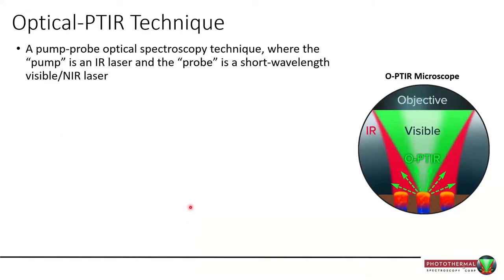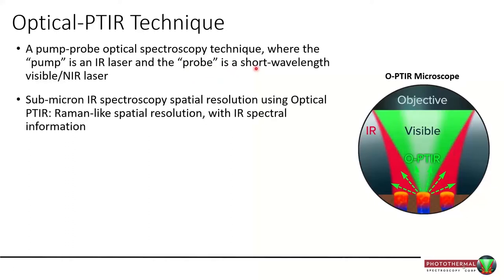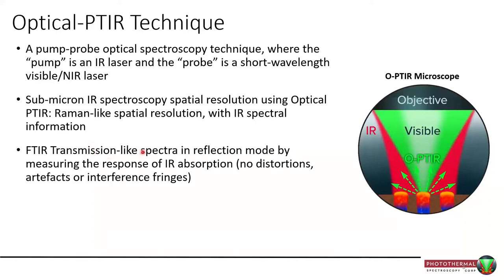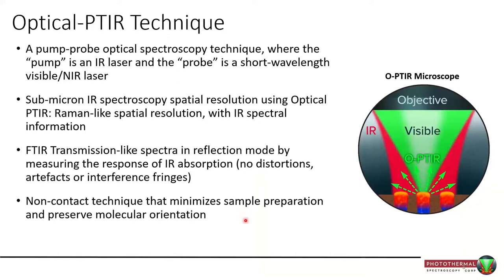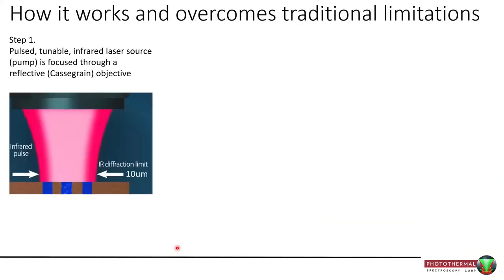Enter the OPTIR technique. It is a pump-probe optical spectroscopy technique where the pump is an infrared laser to excite the sample and the probe is a short-wavelength laser to probe the sample. It delivers submicron microscopy — very much like a Raman microscope — but delivers the infrared richness of infrared spectroscopy. Spectra are very much like regular FTIR transmission spectra but delivered in reflection mode without distortions, artifacts, or interference fringes. It is non-contact, far-field, and spatially resolution is wavelength independent.